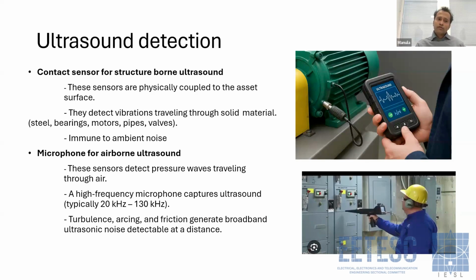But when it comes to the microphone, or airborne ultrasound, we need microphones. In that case, we don't measure directly on the sound source. Instead, we measure the pressure waves which have been generated by the structure-borne ultrasound or the sound source itself. So it provides a safe alternative for measuring ultrasound.